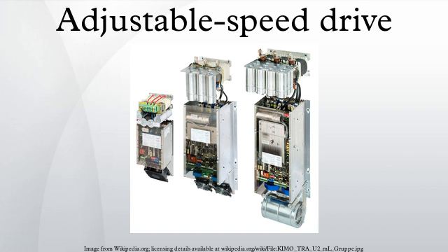Eddy current drives are slip-controlled systems, the slip energy of which is necessarily all dissipated as heat. Such drives are therefore generally less efficient than AC-DC-AC conversion-based drives.